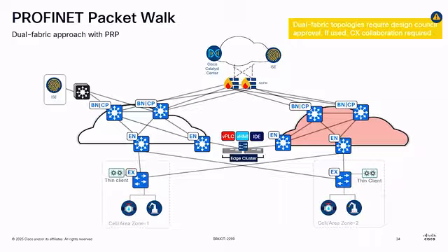Yeah. So how far is your virtual PLC? Is it in the cloud, or where is it? That's a good point. This edge cluster that we see here can be up to 10 kilometers away right now based on our deployments. It kind of depends on how far it is. The latency in between increases by about 5 microseconds per kilometer if you use dark fiber, as we do. In this case, the maximum is 10 kilometers plus some other latency on top, so we are usually below 100 microseconds.